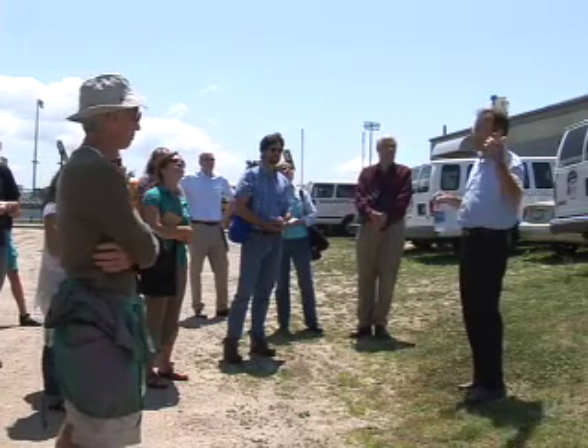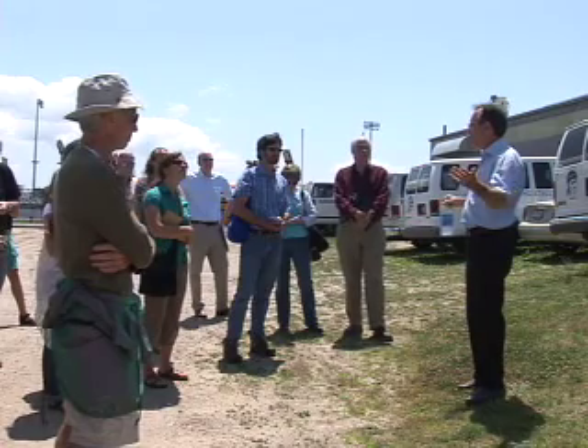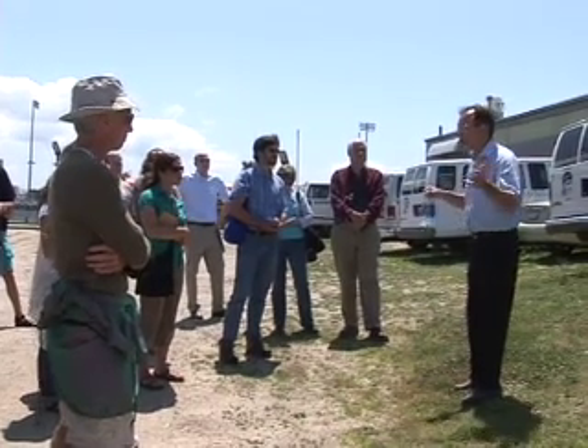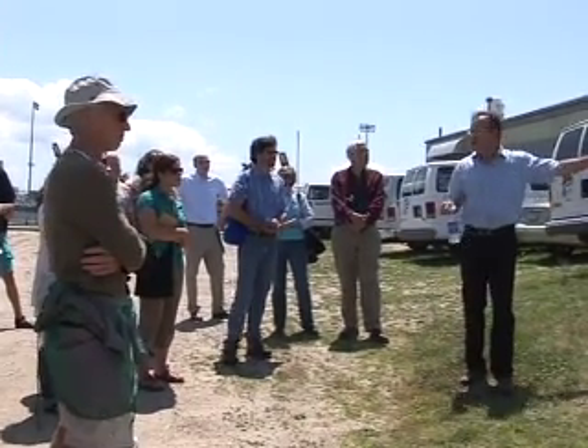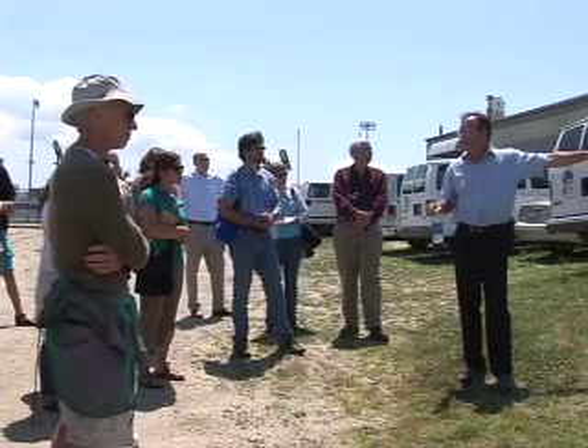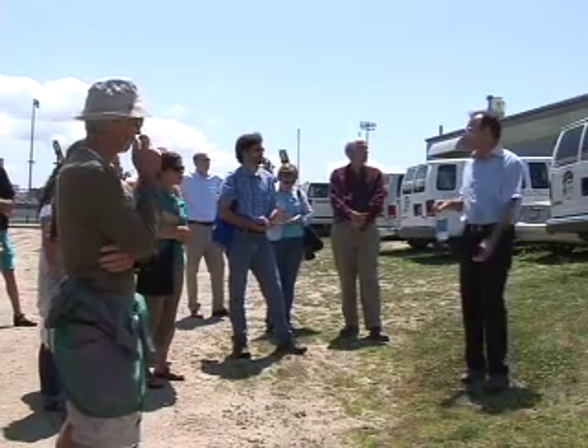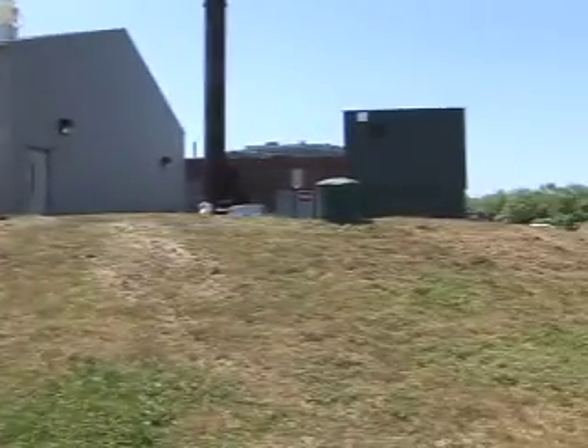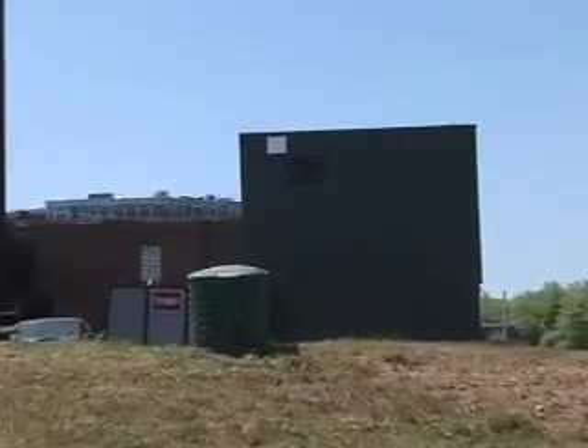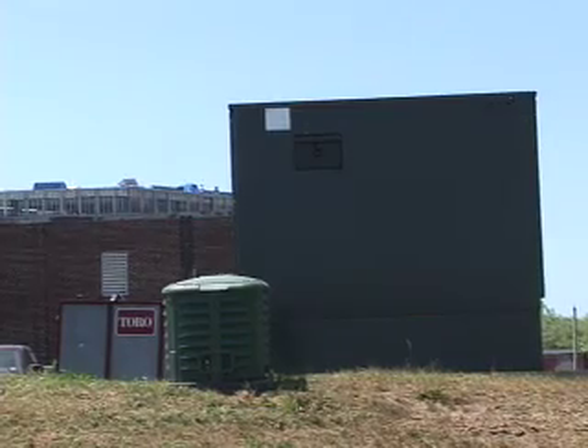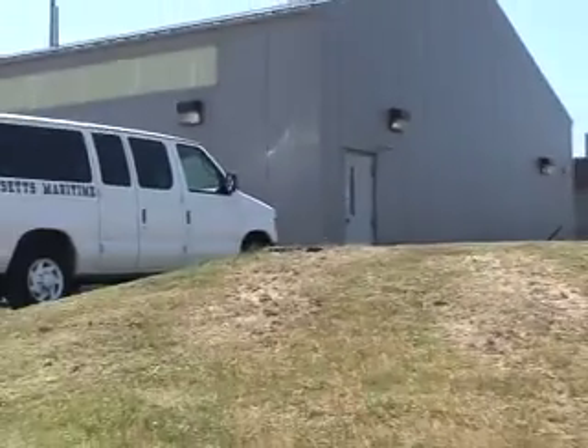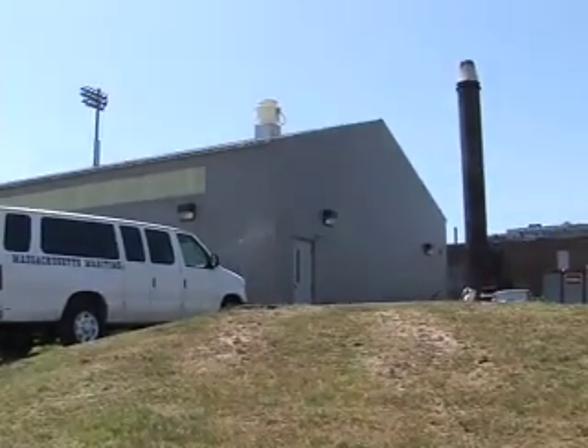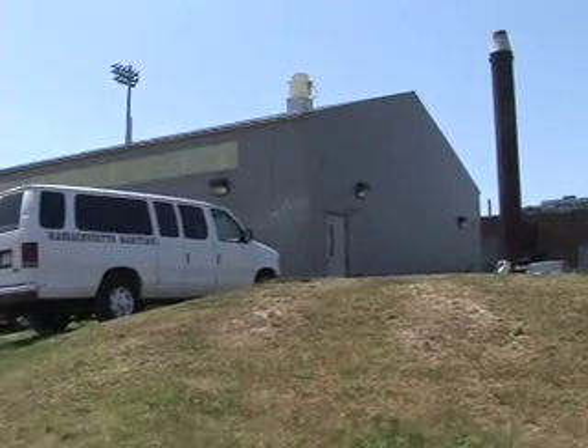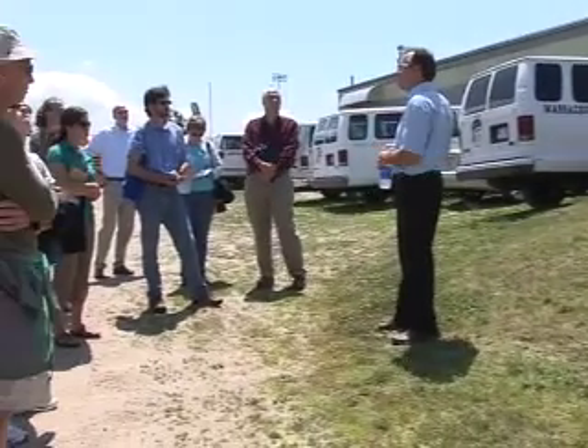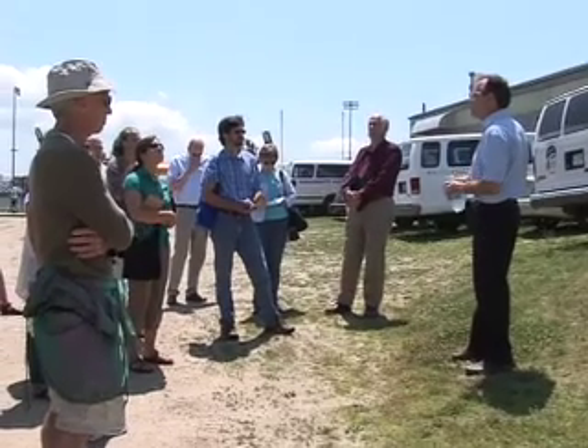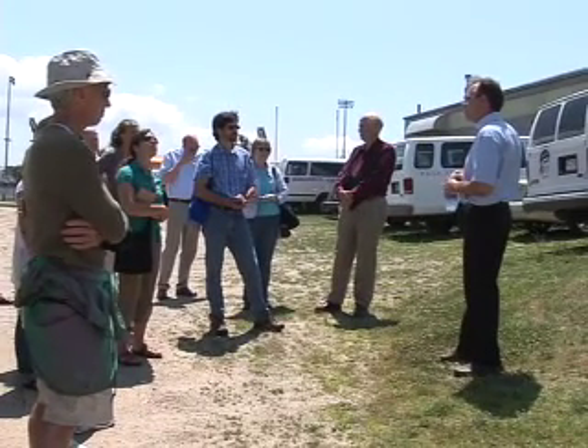This turbine generates 690 volts AC, 3-phase. We need 4,160, so we have a transformer right here. This green equipment, one is a transformer that steps the voltage up to what we need, and the other is a switch. We simply tied into an electric feeder that runs between our power plant and our gymnasium. We had enough spare capacity on that line, and we were able to just tie into it.